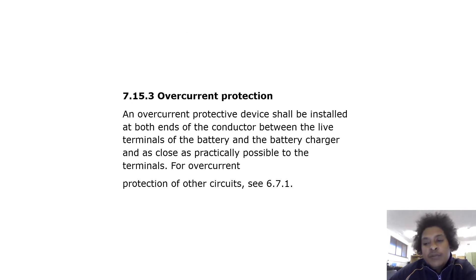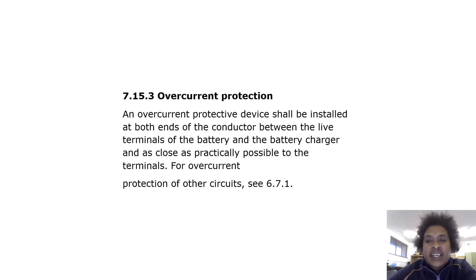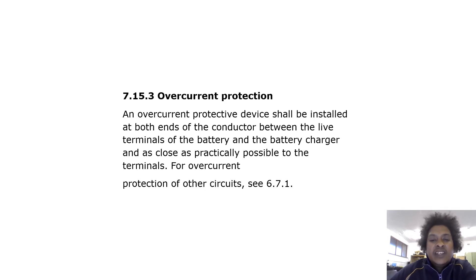Overcurrent protection: an overcurrent protective device shall be installed at both ends of the conductor between the live terminals of the battery and the battery charger, and as close as practically possible to the terminals. For overcurrent protection of other circuits, see Section 6.7.1.